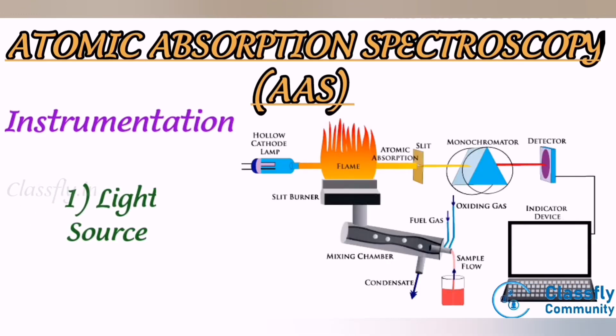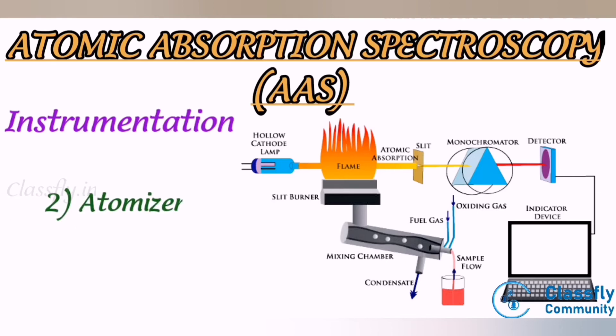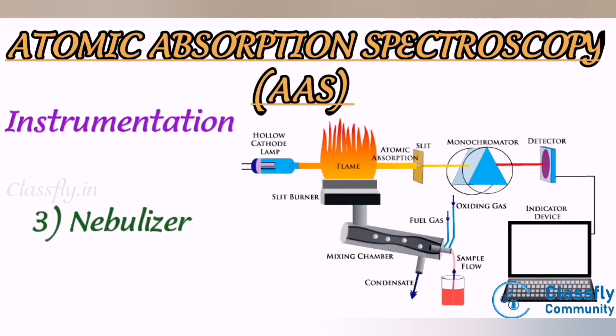Instrumentation. First, light source: hollow cathode lamps are the most common radiation sources in AAS, containing a tungsten anode and a hollow cylindrical cathode made of the element to be determined, sealed in a glass tube filled with inert gases; each element has its own unique lamp. Second, atomizer: elements to be analyzed need to be in an atomic state; atomization is the separation of particles into individual molecules and breaking those molecules into atoms, done by exposing the analyte to high temperature in a flame or graphite furnace.